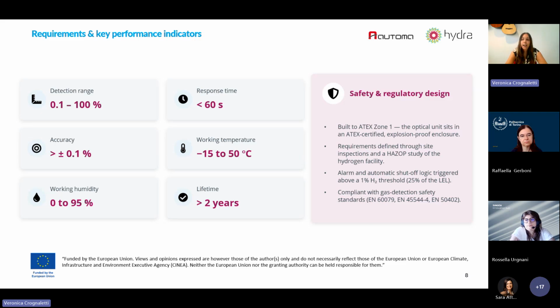So we need an ATEX Zone 1 certification in order to work in hazardous conditions. We have a requirement defined through site inspection and also with an HAZOP study. As I said, we also need an alarm that is triggered above the 1% hydrogen threshold, and we need to comply with the gas detection safety standards.